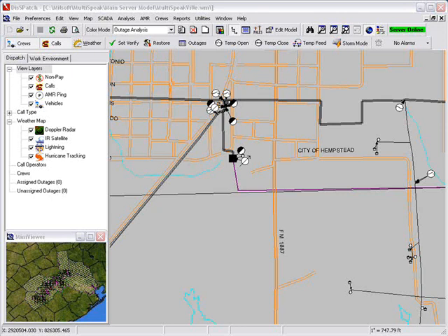states in dispatch. But what if no breaker operation occurs and the substation voltage drops or the substation loses its feed from the transmission system? In this case, no breaker operation had occurred, but dispatch is still capable of detecting a substation outage based on analog change notifications from the SCADA system.